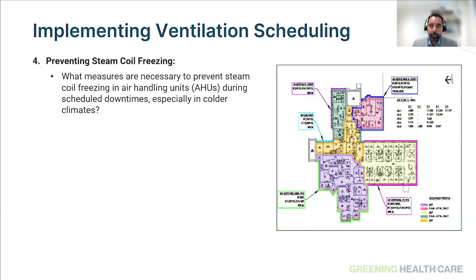Other questions that we got through these conversations with the hospitals are around steam coil freezing. Some of your systems have steam coils that, if they're shut down at nighttime during a cold day, a startup will cause the freeze stat to trip, and sometimes it may cause the steam coils to freeze. So can you do that in colder weather for your systems?